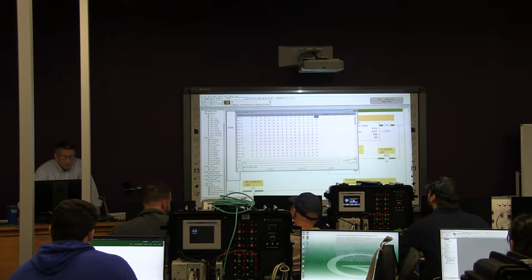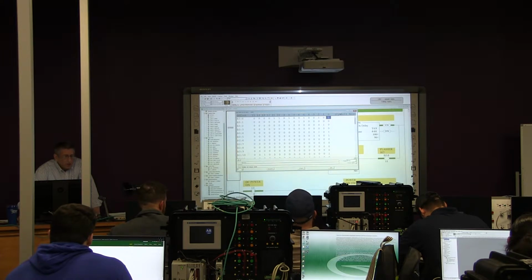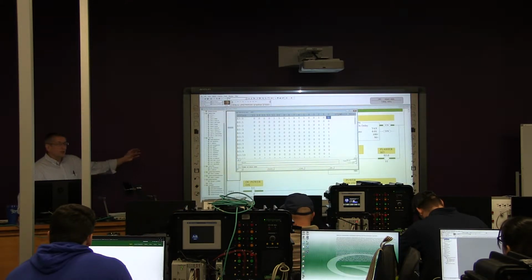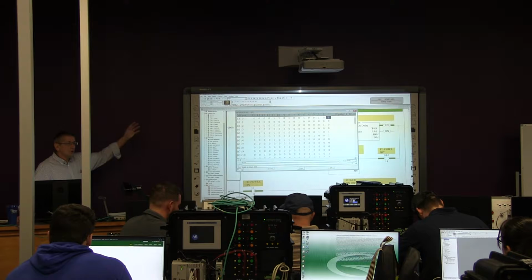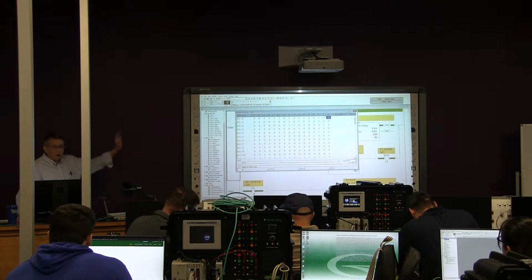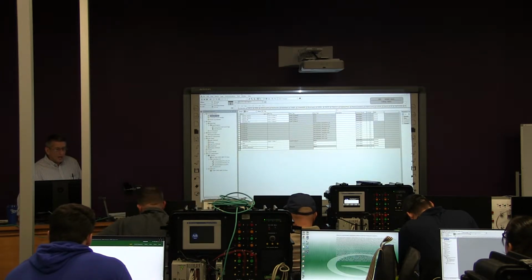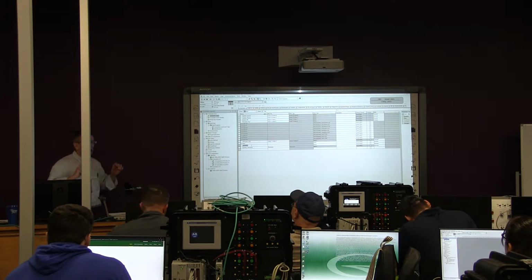So in the 500, in the MicroLogix, this is what you got, right? You have all these fixed addresses, and they are a piece of memory that's just dedicated to addressing. That's all it's for. But over in CompactLogix, we set up tags. The tags become the address. They're not really addresses because they move around.